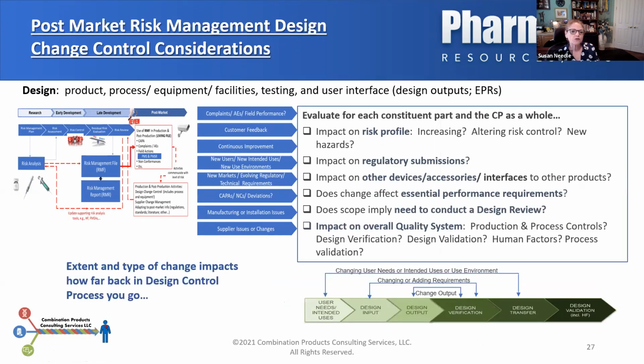So as you go forward with your change control, you want to evaluate the impacts for each constituent part and the combination product as a whole. Evaluations of your risk profile, new hazards, new harms, the increased severity of the harms. Look at regulatory submission impacts and other devices, accessories, and interfaces that might be brought into the mix as being impacted. What about your essential performance requirements? And how far back do I have to go in my device design control process based on the change that's being made? My change might require that I redo some of my design verification activities. It might require that I go back and look at my design input requirements. It may trigger me to have to go back and redo my entire design control process all the way back to my user needs and intended uses and intended use environment. So you really have to pay attention to every change that you're making and assess how far in the process it is causing you to go back and redo.